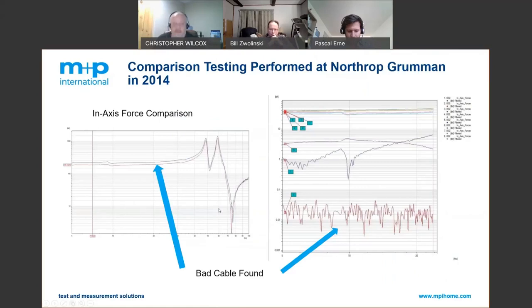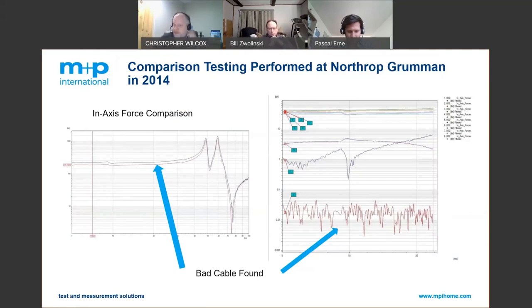In 2014, during a test using an existing system, on the very first run of the day with our new system, the forces did not match. It turned out there was a bad cable. The summing junction had hidden this issue — the sensitivity had been adjusted to calibrate around the bad sensor — but nobody had ever caught it.